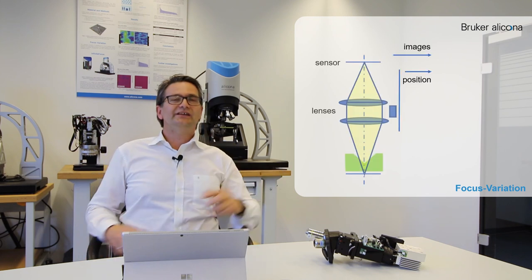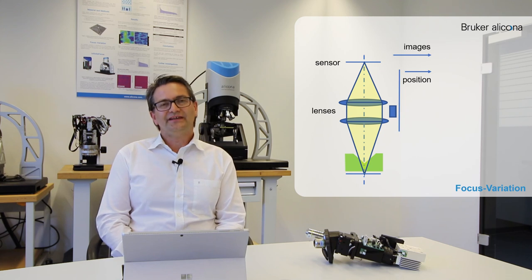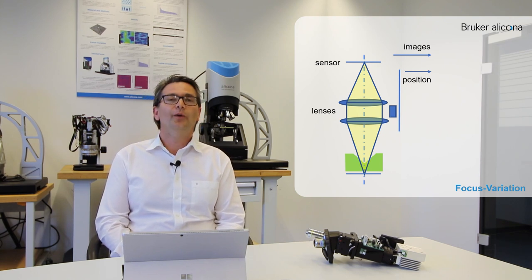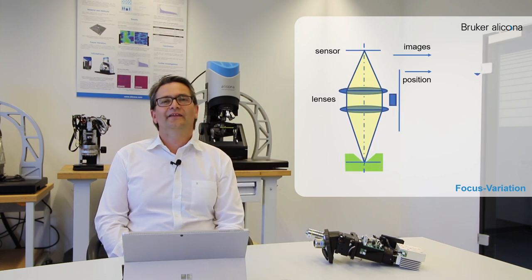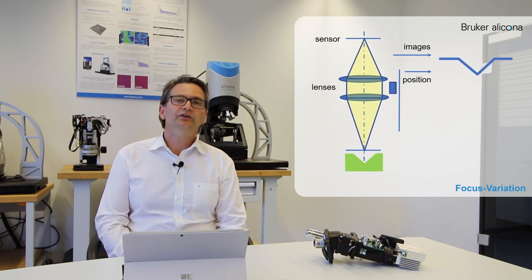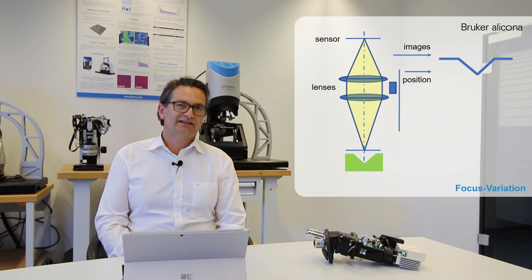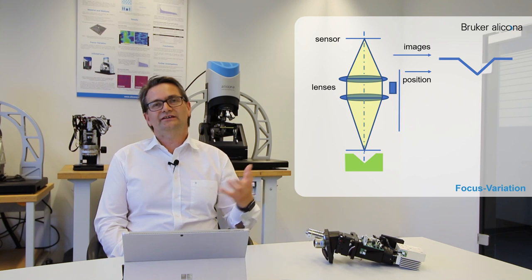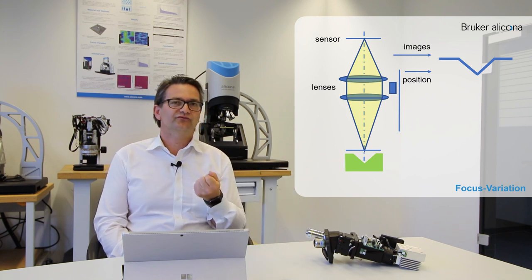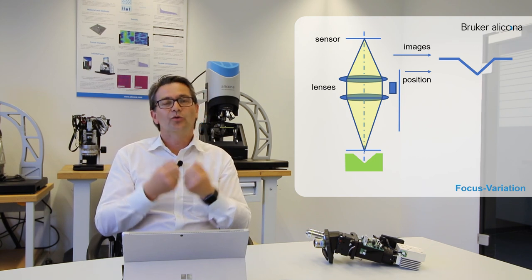Let's take a look at the complete system and how it really works. On the graphics here you see the optics, the lenses, the sensor, and an object. The whole optical setup is moving upwards, and a linear encoder is mounted to record the length that the optic has moved. The software acquires images from the sensor and data from the high-accuracy linear encoder, combining these to generate a 3D data set.